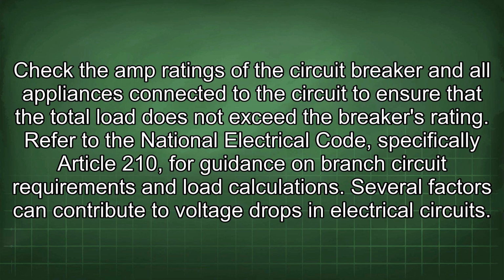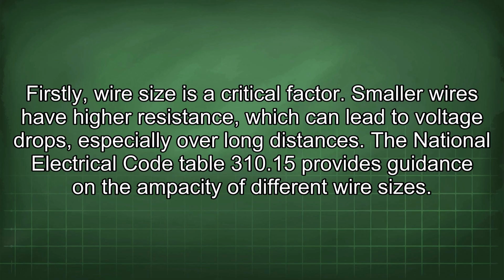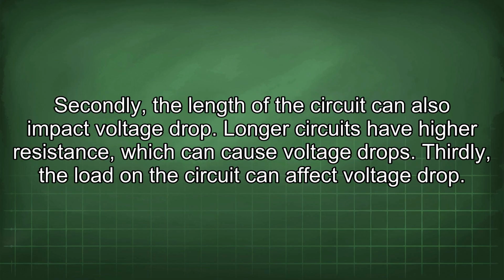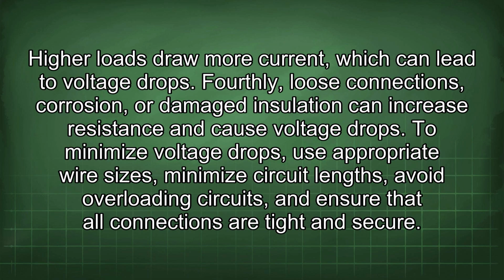Several factors can contribute to voltage drops in electrical circuits. Firstly, wire size is a critical factor. Smaller wires have higher resistance, which can lead to voltage drops, especially over long distances. The National Electrical Code Table 310.15 provides guidance on the ampacity of different wire sizes. Secondly, the length of the circuit can also impact voltage drop. Longer circuits have higher resistance, which can cause voltage drops. Thirdly, the load in the circuit can affect voltage drop. Higher loads draw more current, which can lead to voltage drops. Fourthly, loose connections, corrosion, or damaged insulation can increase resistance and cause voltage drops.